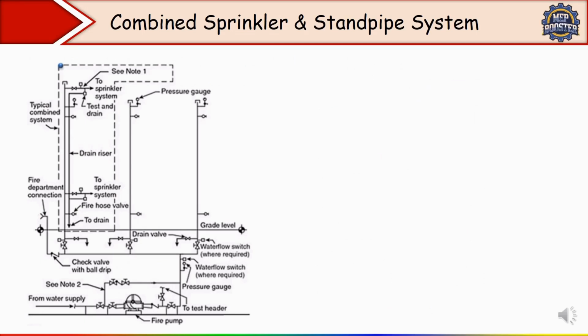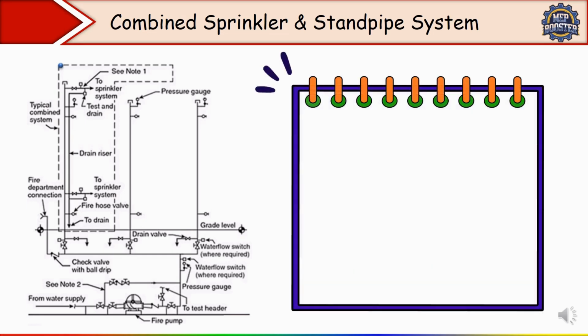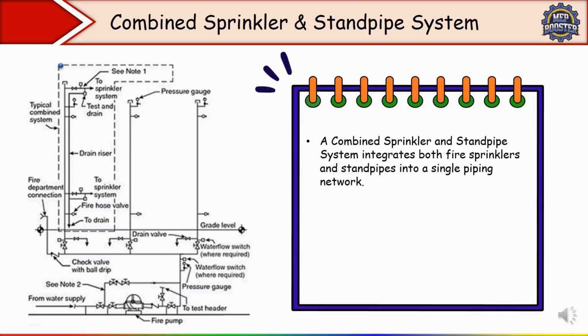So here first of all, we'll discuss what is actually combined system. See, a combined system means what? A combined sprinkler and standpipe system integrates both fire sprinkler and standpipes into a single piping network. Okay, you can see in this image. Here it is written, a combined sprinkler and standpipe system integrates both fire sprinkler and standpipes into a single piping network. Okay, if you see here in this image, here we have both pipes, fire sprinkler pipes are also going in each and every floor. Even see we have placed the standpipe.